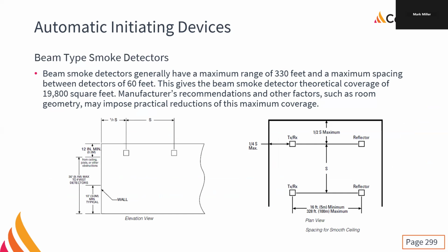But like a standard smoke detector, not an extra range or anything like that, a standard smoke detector will go about 330 feet, round about 100 meters without even trying. The only thing we have to do is put a larger reflector on. So instead, a standard reflector is about 8.5 by 11 sheets, and the large reflector is just four of them. Right, and that's all that we have to do to get it to work to that kind of range. A 100-meter long room is really big.